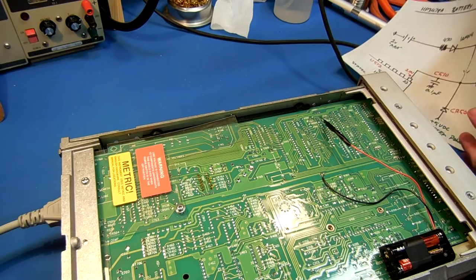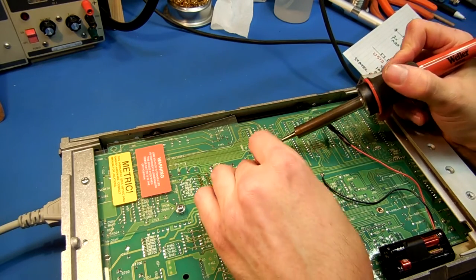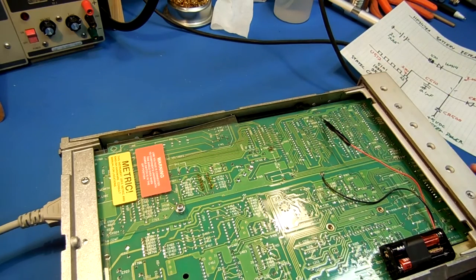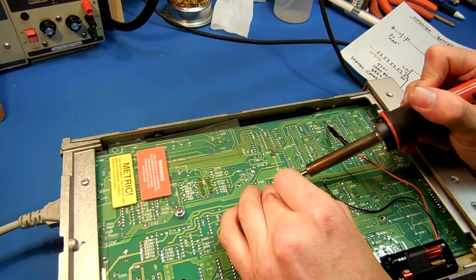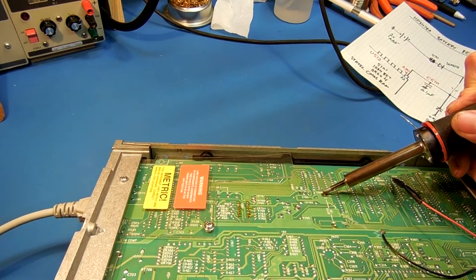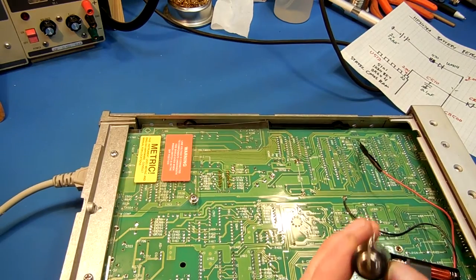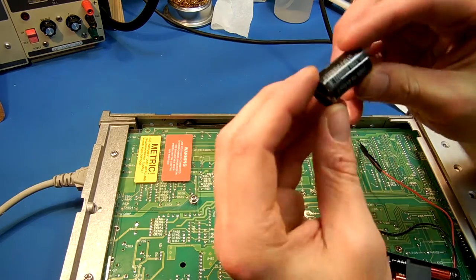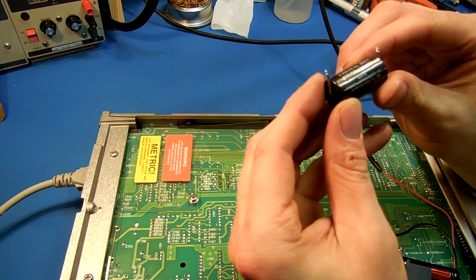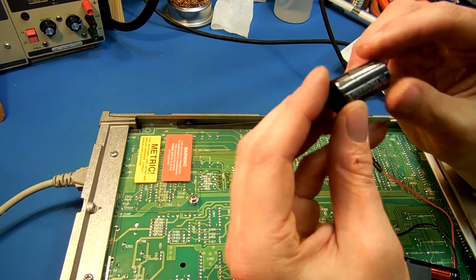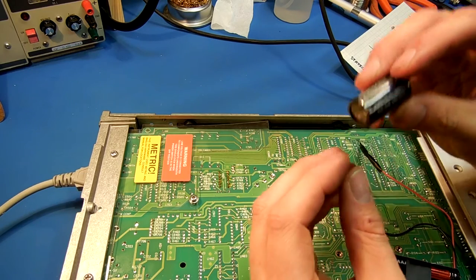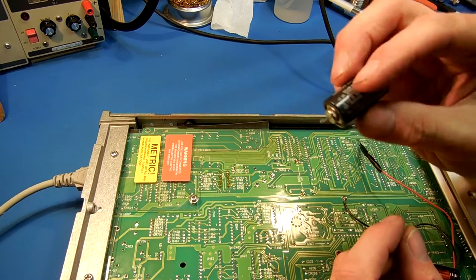Now to remove the battery. Helps to add a little bit of, I'll probably do the ground first. Helps to add a little bit of solder to it. Let's see if we can just pull it right out of the bottom. Yeah, it just dropped right out. There's the original battery. Internal cell, lithium cell. What do you think it has HP part number on it? No date. But I imagine it's, this is a earlier model HP 3478A. So I betcha it probably around, you know, 1985 or so. It's, you know, pushing way more than the 10-year limit.